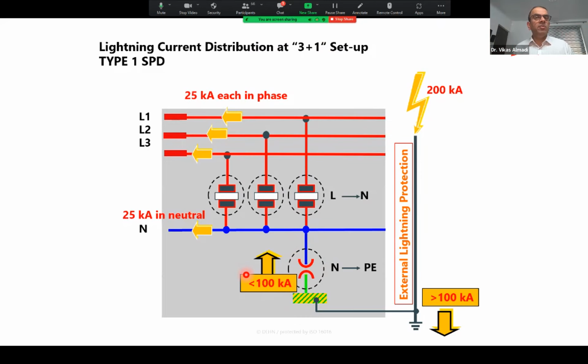It's not that they will have zero current, but very, very less, like 1 kiloampere, 1.5 kiloampere. Otherwise, the cable themselves will not be able to withstand those currents. So here you see the current, 50%, that is 100 kiloampere, will try to go through this arrestor. So this arrestor has to be rated for 100 kiloampere, not to forget 10/350 microsecond.